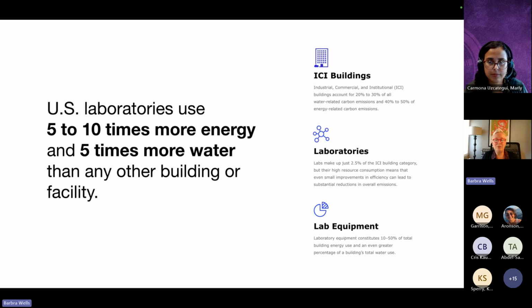All this results in the numbers you see here on this slide, which are based on a comparison of consumption by square footage. Some specialty labs, like clean rooms, can use up to 100 times more energy than a similarly sized ICI building. When it comes to water, high laboratory consumption is largely due to the need for washing and rinsing equipment, cooling systems, RO water systems, and steam generation.